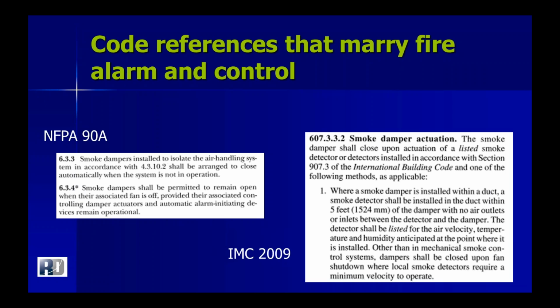And maybe one reason is that the control aspect and the fire alarm aspect are these two code references, NFPA 90A and the IMC 2009, with these sections identified here. And most importantly, if we just look at the paragraph on the left-hand side, 6.3.4, it's talking about fire smoke dampers being permitted to remain open when the fan is off, provided that the controlling actuator and alarm devices remain operational. So the question is, do all the devices remain operational during all operating conditions?